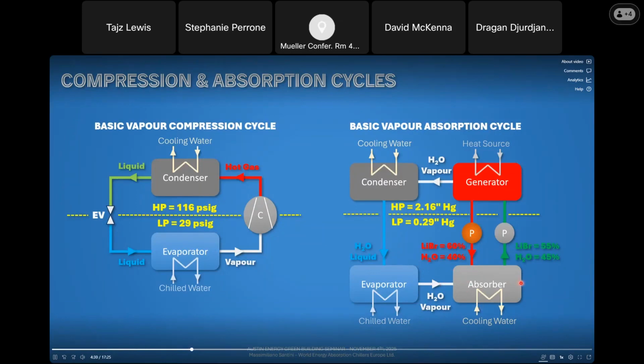The diluted solution from the absorber is then pumped to another heat exchanger, the generator, where it finds the heat source. Thanks to the high temperature of the heat source, the refrigerant vapor is separated from the diluted solution, and thanks to this separation, the refrigerant vapor can reach the condenser and return to the liquid state. At the same time, after the refrigerant separation, the solution gets concentrated again back to 60% to restart the absorption process.